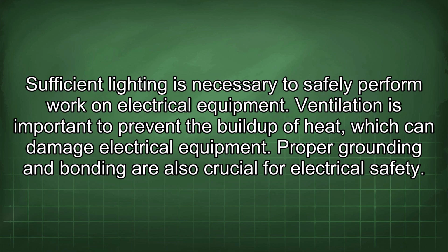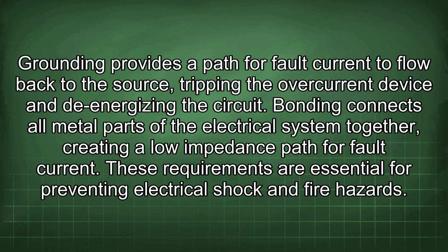Proper grounding and bonding are also crucial for electrical safety. Grounding provides a path for fault current to flow back to the source, tripping the overcurrent device and de-energizing the circuit. Bonding connects all metal parts of the electrical system together, creating a low impedance path for fault current. These requirements are essential for preventing electrical shock and fire hazards.